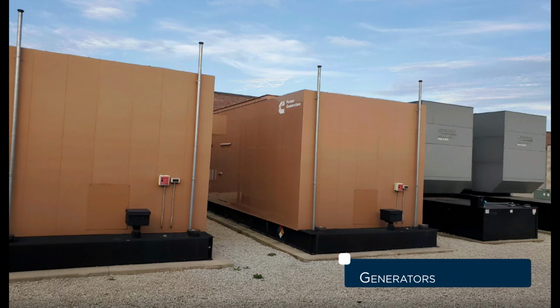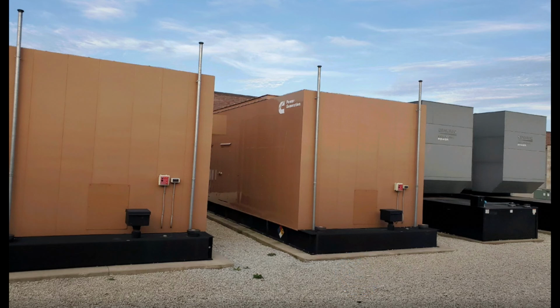In the power yard, all UPS power is backed by generators. The power transformers, generators, and cooling systems are protected by a 20-foot high break wall. The A side and B side each have their own generators, and we have 48 hours of reserve fuel capacity for the entire facility. There are 2 sets of generators that support the 2 power feeds.